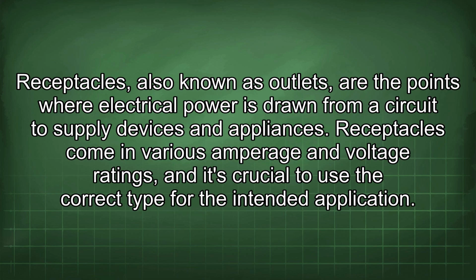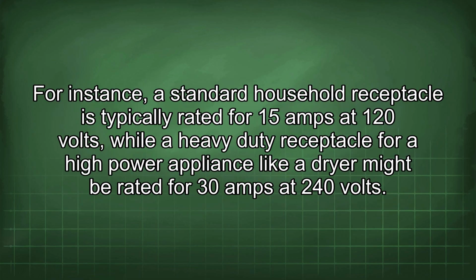Receptacles, also known as outlets, are the points where electrical power is drawn from a circuit to supply devices and appliances. Receptacles come in various amperage and voltage ratings, and it's crucial to use the correct type for the intended application. For instance, a standard household receptacle is typically rated for 15 amps at 120 volts, while a heavy-duty receptacle for a high-power appliance like a dryer might be rated for 30 amps at 240 volts.